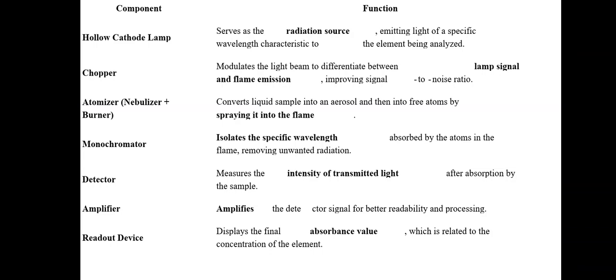Next unit is amplifier. Amplifier amplifies the detector signal for better readability and processing. Readout device displays the final absorbance value which is related to the concentration of the element.